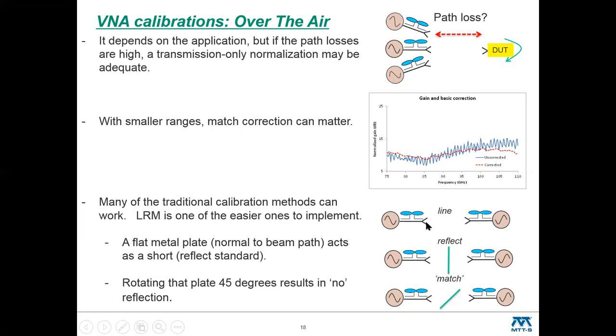But if you think about it, a line is sort of easy—you're just pointing your two antennas at each other. A reflect could be a short, essentially a metal plate normal to the path. An important point about this algorithm family is you don't really need to know much about this reflect standard—it's not like short-open-load where you have to specify the S parameters. It really just requires the reflect to be symmetric.